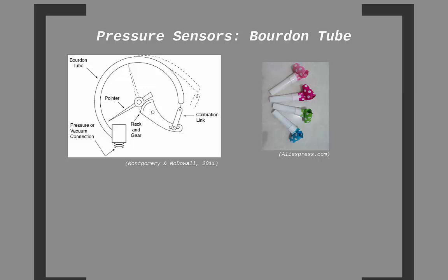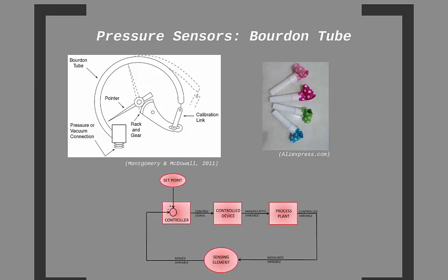The extension will cause a mechanical change in the device, such as the positioning of the pointer needle. That position can be used as an indicator of fluid pressure for monitoring purposes, or that mechanical change can be converted to a more usable signal format to be sent back to a controller where the sensor is to be used in a control loop. Such a conversion again would occur in a transmitter.